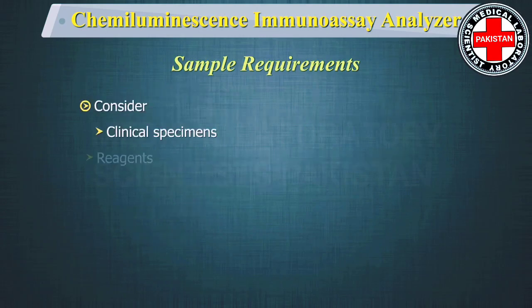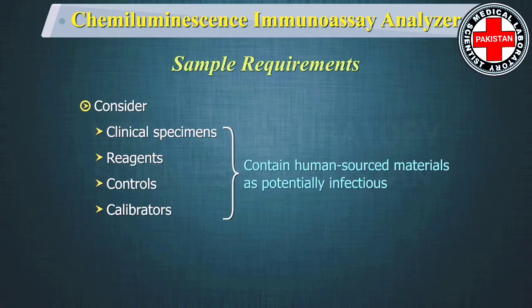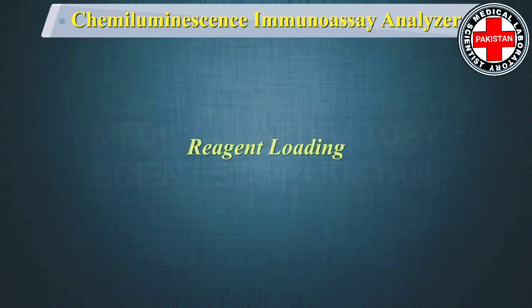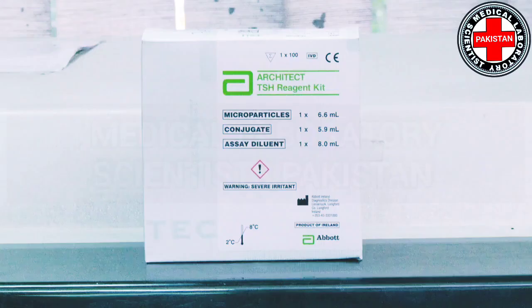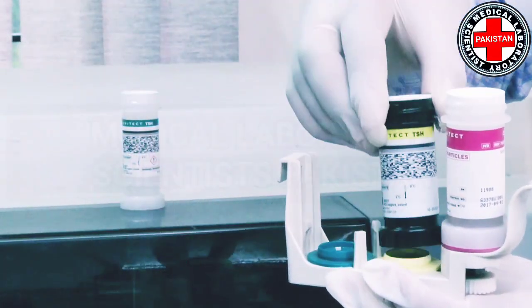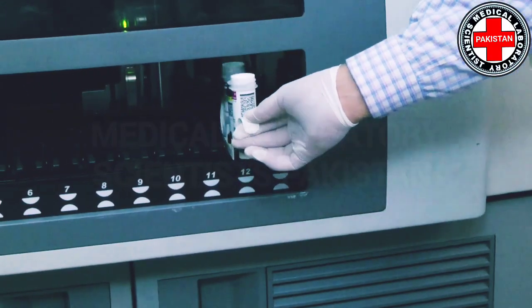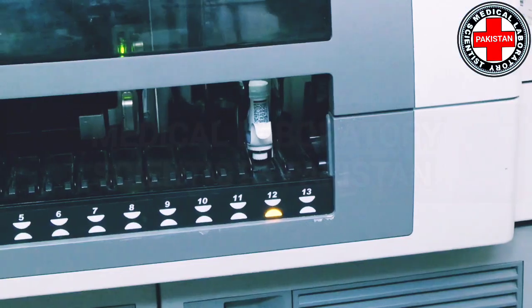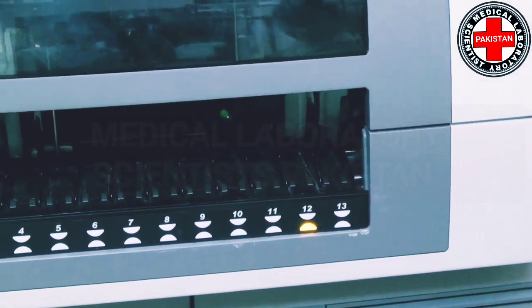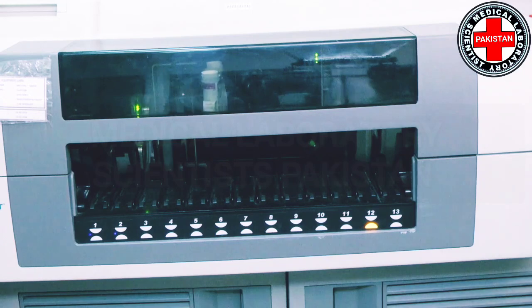Consider all clinical specimens, reagents, controls, and calibrators that contain human source materials as potentially infectious. The TSH reagent kit includes the microparticle reagent, the conjugate, and the assay diluent. Place reagent bottles on the matching coloured sections of the reagent carrier and load them into the machine. The carrier transport picks up the carrier and moves it past the barcode reader, which identifies the reagent kit, and the carrier transport loads the carrier onto the reagent carousel.